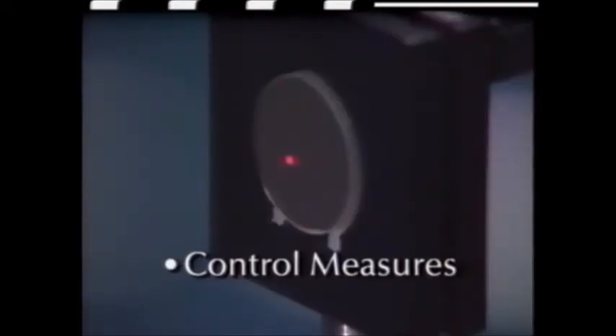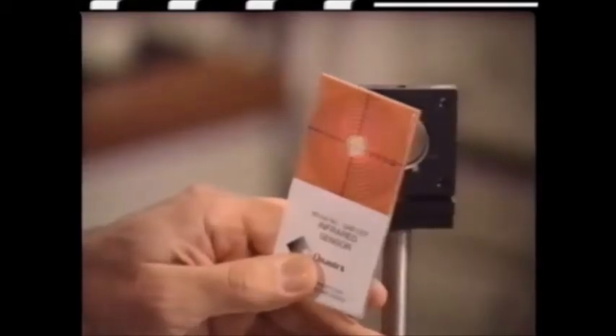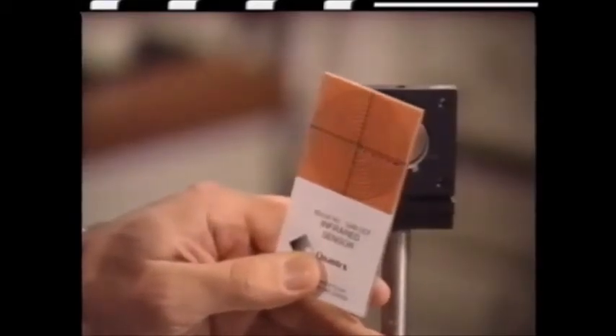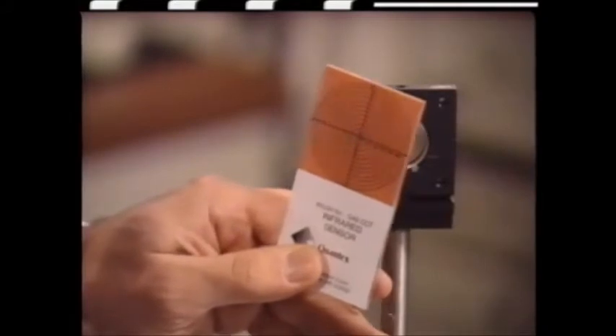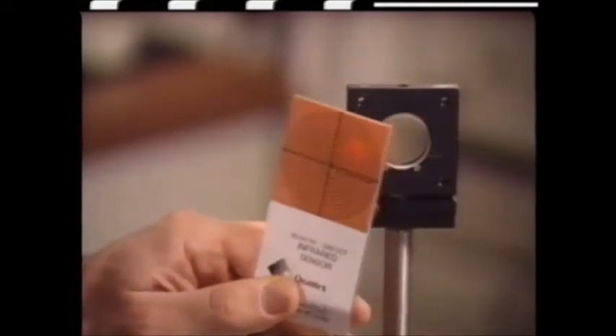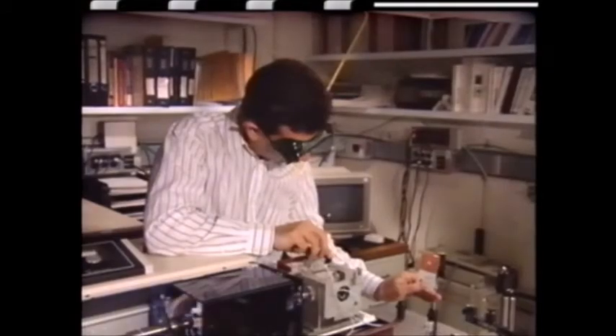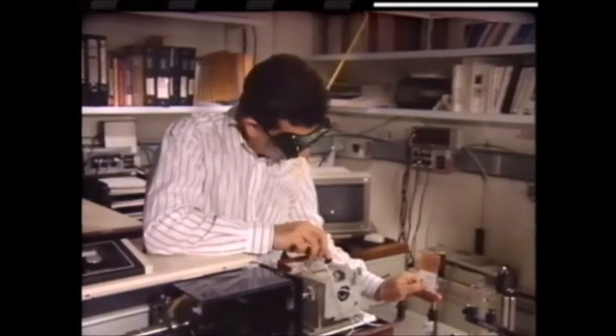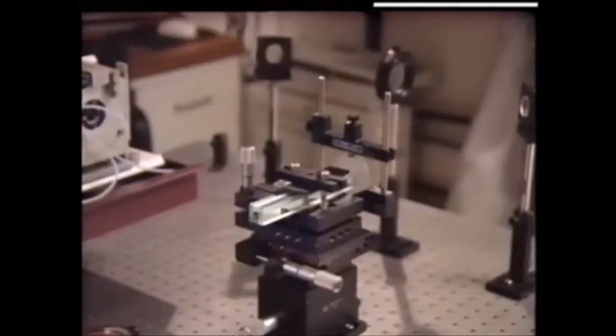Use low-powered lasers with visible emissions. Use cards for the safe viewing of diffuse reflections from low-powered Class 3B lasers. Use sensor cards that fluoresce or re-radiate energy at a different wavelength from the originating beam. This allows you to safely view the beam through protective eyewear. Use an infrared imaging scope to safely view the diffuse reflection of the beam through protective eyewear.